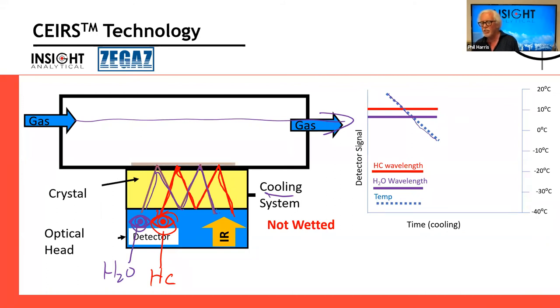In this case, we're going to see that when hydrocarbons start to show up on the layer, and I've tried to show the hydrocarbons as that little brownish layer on the surface, hydrocarbons drop out on the surface because the crystal is cool. It has just hit the hydrocarbon dew point. So now hydrocarbons drop out of the surface, and the wavelength of light that interacts with hydrocarbons changes its intensity. The light gets absorbed by the hydrocarbons.